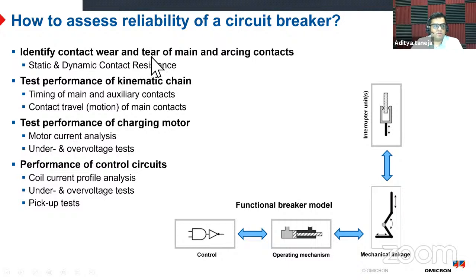That we can check by doing dynamic and static contact resistance measurement. This is one test which we should do, both of them actually, because high voltage breakers have an assembly of main and arcing contacts. Main contact health can be seen by static resistance measurement, and arcing contacts can only be seen by dynamic contact resistance measurement without opening the circuit. I'll talk about these tests in detail.